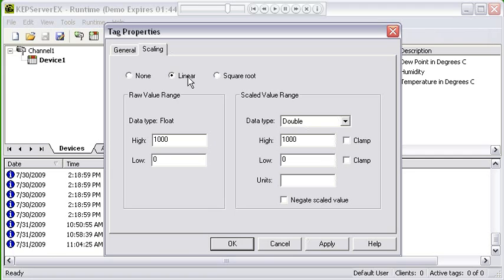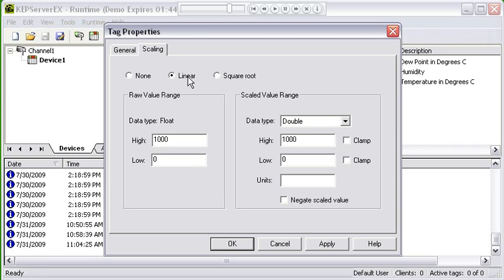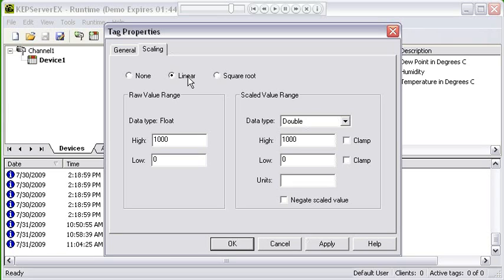You choose the data type that you want and you can clamp the scale values. We do this because sometimes an input will actually send a value higher than the expected or calibrated high value point, and when you start getting above that set value, the actual scale value will start to deviate due to the way the mathematics works for the scaling. So you might want to just clamp that, or you may not want to show anything that goes higher than your scale value is. If you clamp it, anything that goes higher on the raw side is just going to be clamped at the scaled high value side.